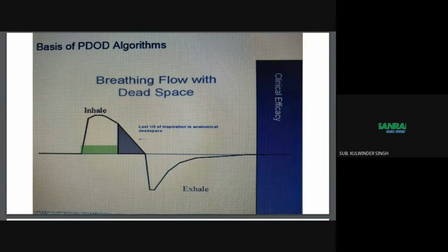So they are also coming in 2 variants. One is the fixed per breath dose delivering machine, and the other are the fixed per minute dose delivering machines. So in the fixed breath dose machines, we see OxLife Independence by O2 Concepts, which delivers a fixed dose of oxygen per breath. If we see at setting of 2, it delivers nearly 32 ml of oxygen per breath, but it is fixed. It cannot change if the patient's breath rate is changed. In case of fixed per minute delivery machine, that is Inogen, it delivers 420 ml of oxygen at the setting of 2. So that I have already told.